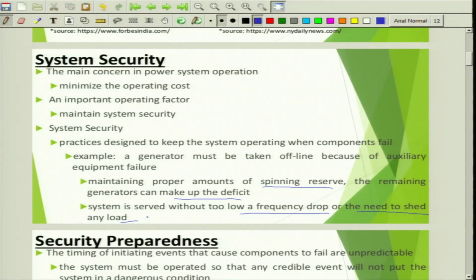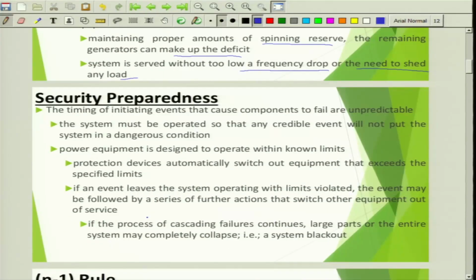So there are two options. If there is a line outage or a generator outage, then either you have to shut down some load, so that you can meet the remaining load with the available generators. The other option is to maintain proper spinning reserve so that you do not allow a sudden frequency drop, and yet you maintain power system security and keep feeding the existing load. The timing of initiating events that cause components to fail is unpredictable. The fault, when it happens and how it happens, we do not know, right. The system must be operated so that any credible event will not put the system in a dangerous situation.